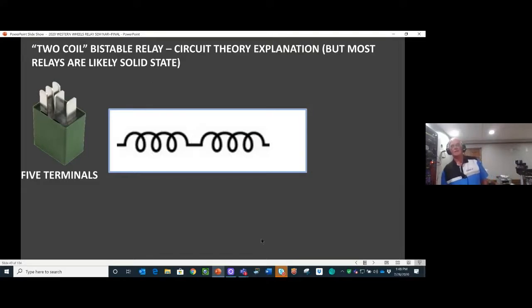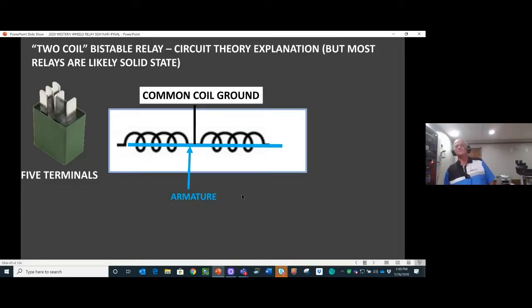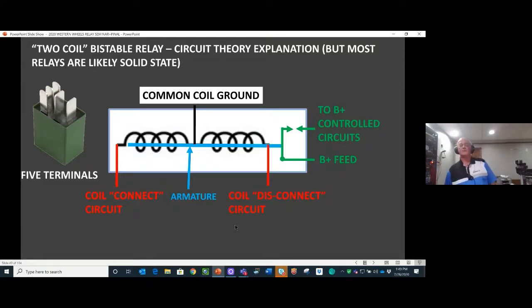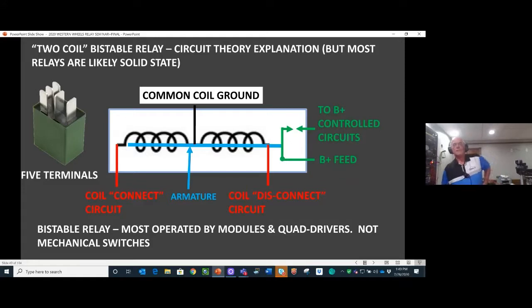But if you want to understand how it works, you've got 2 coils on this relay. You've got a common armature that runs through both coils. And both coils share a common ground. Then we have a set of contacts that the armature either closes or opens, but there's no spring to return them back. It stays wherever it's moved to. So we have one coil connected to one circuit that either turns it on or turns it off. And then we have another coil connected to another circuit that reverses that position. Again, these are momentary coil circuits, just on for a short millisecond or 2. Most are operated by modules, quad driver, or CAN, not mechanical switches anymore.